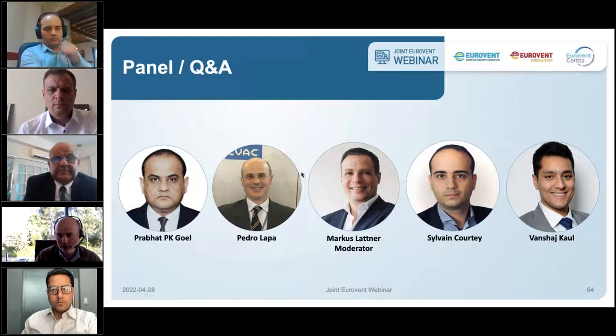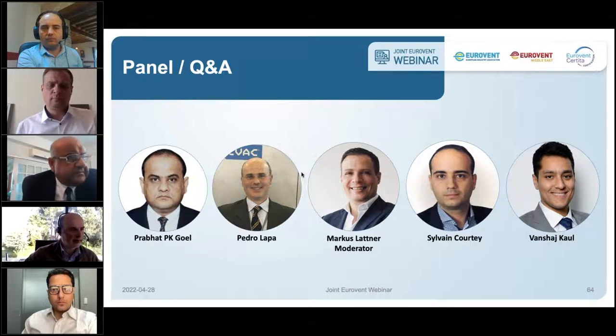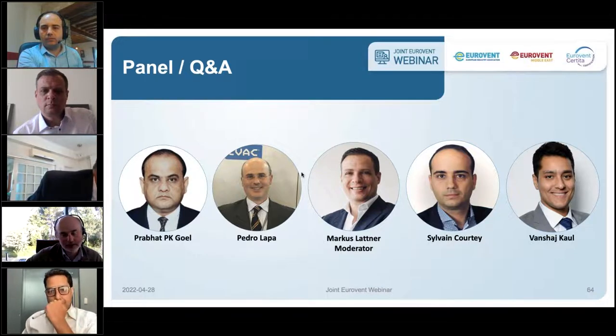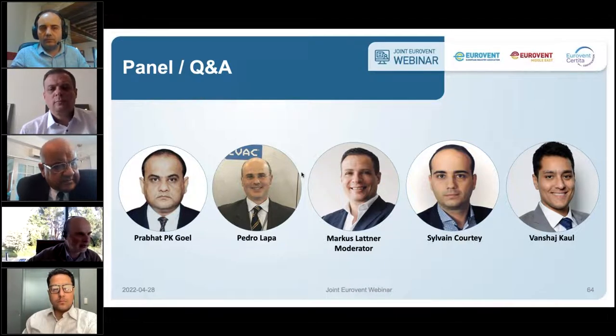So, answering what you asked me about the temperatures, let me look. I have to check in the documents. Give me 1 second, please. So the labeling system as of now, because we are only with one step, the humidity recovery is for the dry winter. It is for the dry bulb temperature in summer bigger than 30 degrees and winter bigger than -3 degrees, or the dew point temperature higher than 17 degrees and dry bulb temperature higher than -3, and the last condition is dry bulb temperature higher than 30 degrees and dew point temperature higher than 17. But that is in the documents, in the table, those conditions.